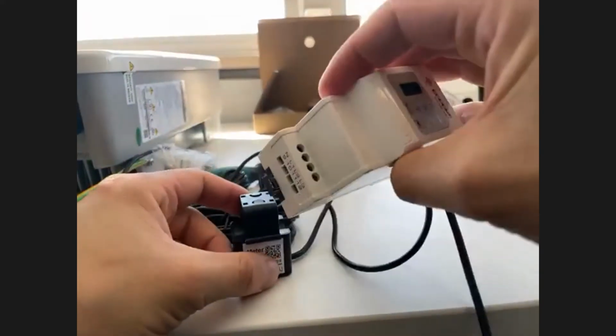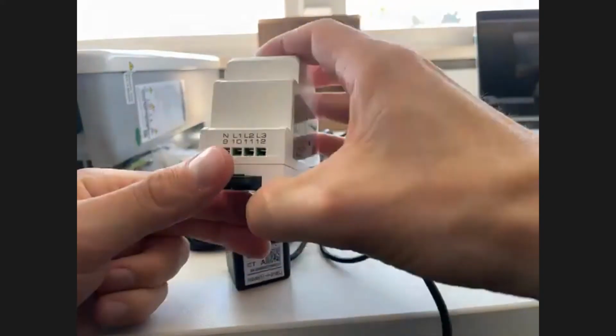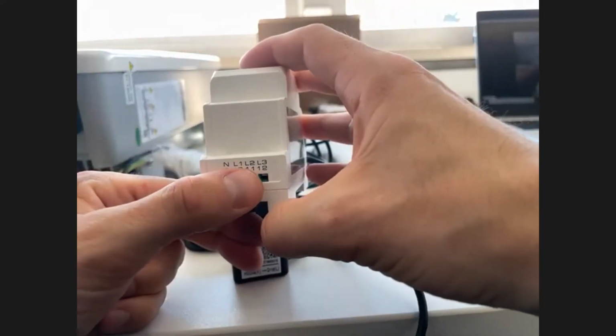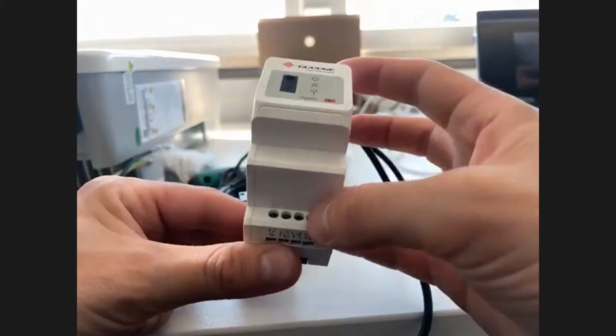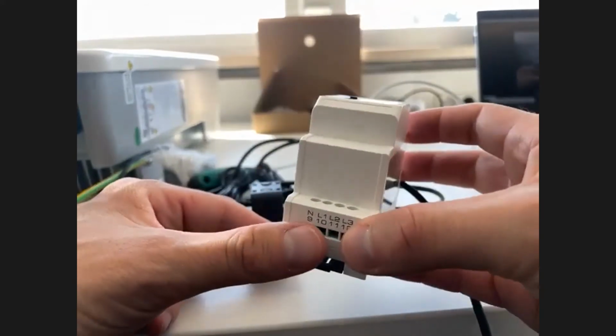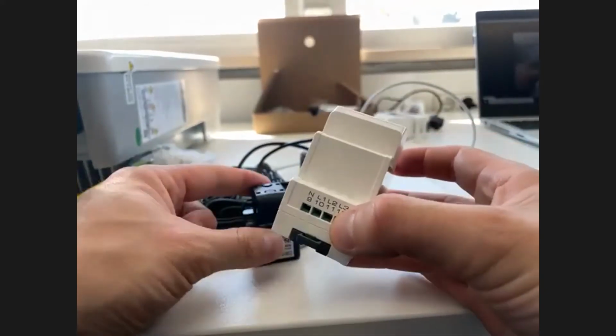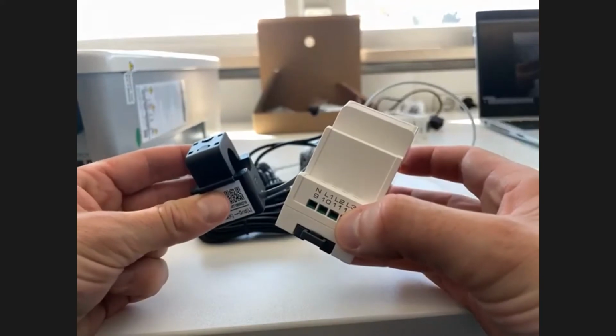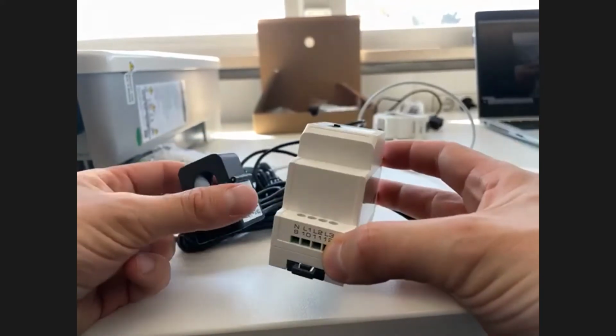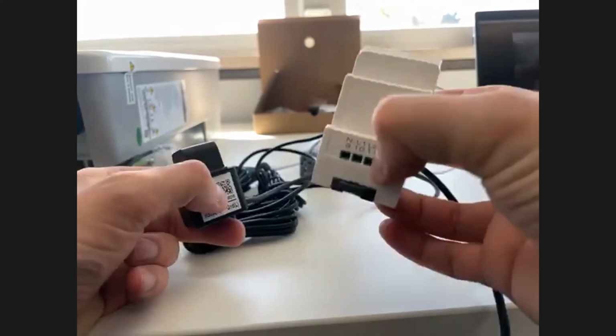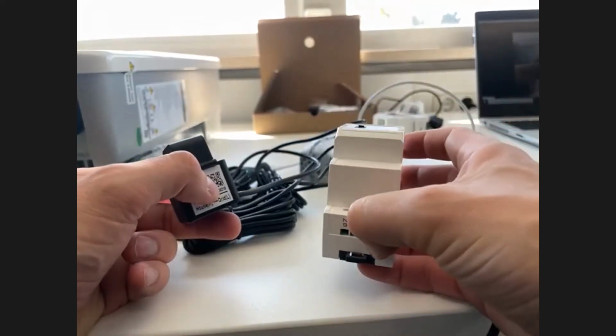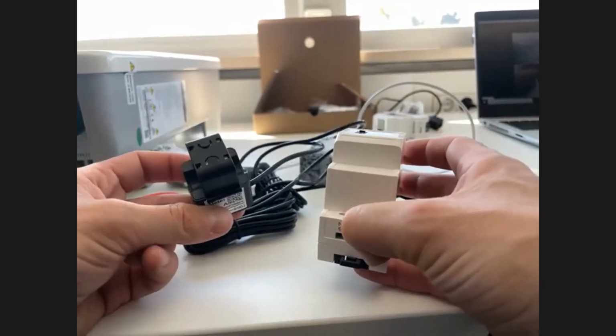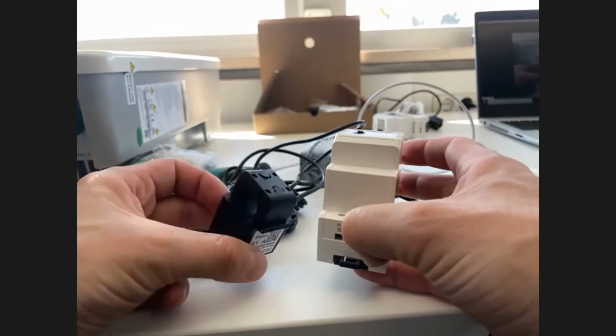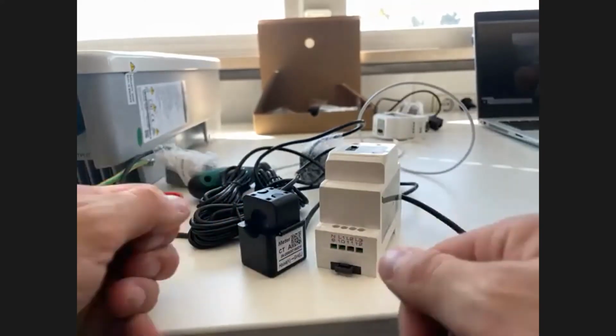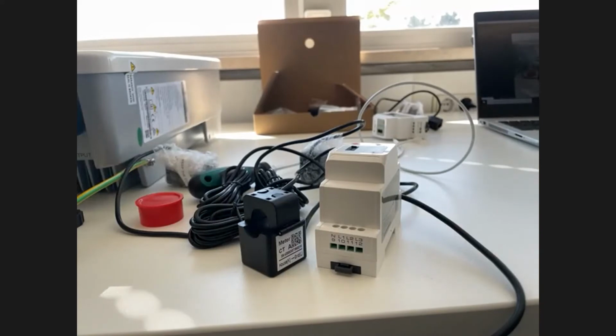And on the bottom side of the smart meter, you see here neutral, L1, L2, and L3. And here you need to connect the voltage sense cables. And they should be connected as close as possible to the CTs. So there should be no loads in between the voltage sense connection to the AC line and the CTs. So they should be in the same position. Yes.